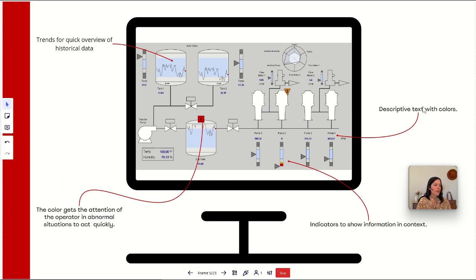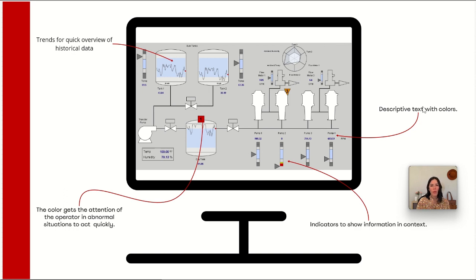We also have descriptive text with colors. This is important because some people on the plant floor can be colorblind, and for them it is too difficult to understand and associate colors with the right alarms in the system. So we have also added descriptive text on the screen, which is also important when environmental issues can cause the screen not to look the way we want.